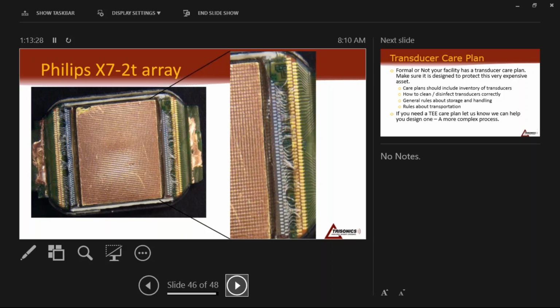If we look at the blow up over here, this is the array, and these are the wires coming from the array to go to the flex circuit. Every one of those individual wires is about the same diameter as a hair. They are non-insulated. They are completely open, and they are suspended in the air. Breathing on them will apply enough pressure to smash them together. You can't even breathe on them.